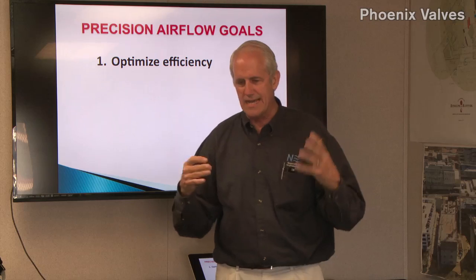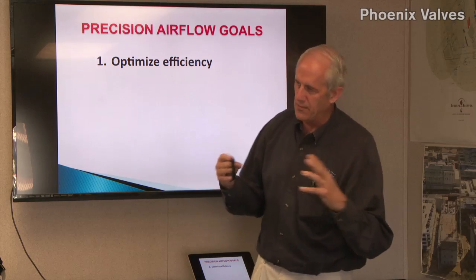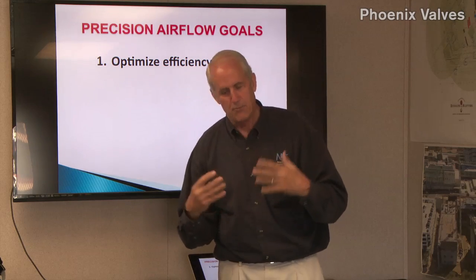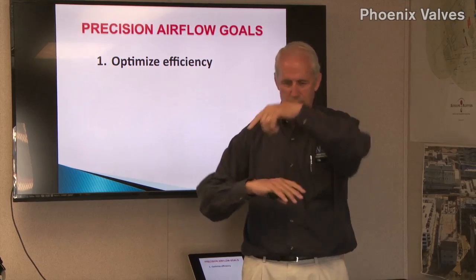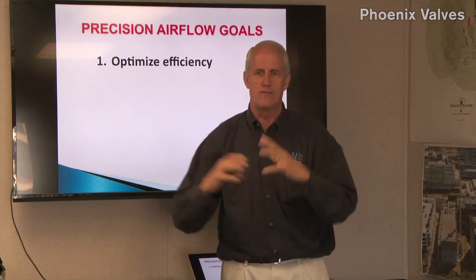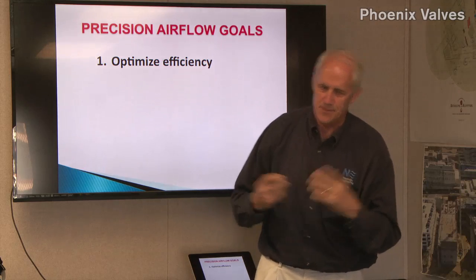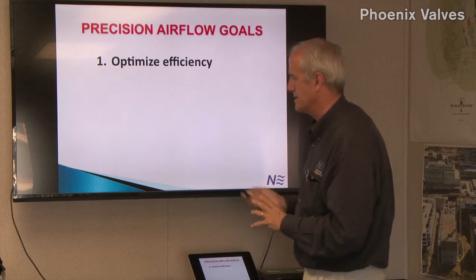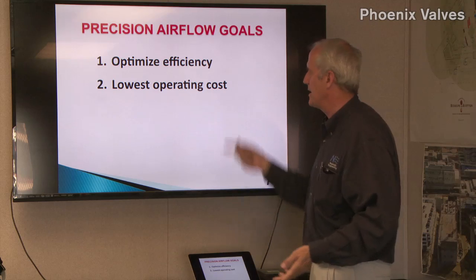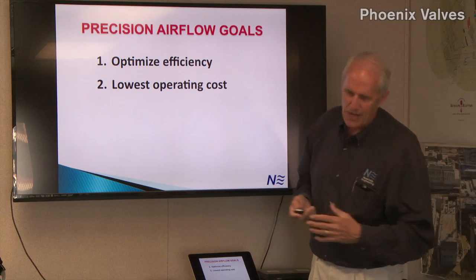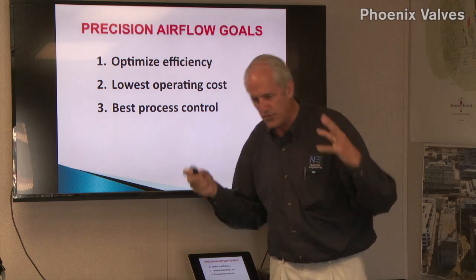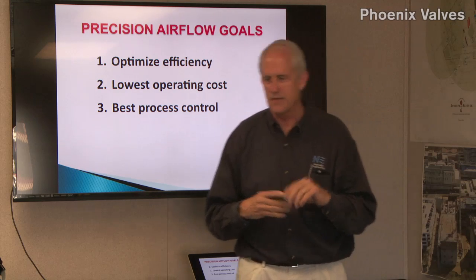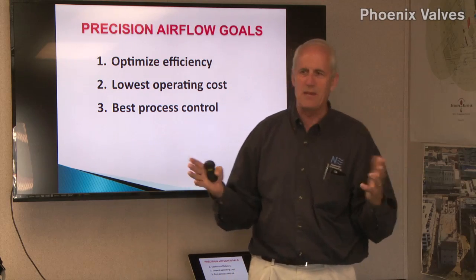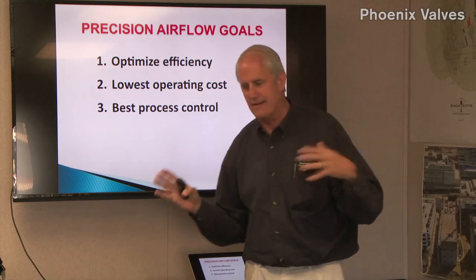So then the question is, how do you respond to it? You do everything you can with your procedures. But when there is an outbreak, you want to make sure that the room gets quarantined, isolated from the rest of the vivarium so it doesn't spread. So that's basically what's going on with the Phoenix valves in this. Anyway, the purpose of the system in general: operate efficiently, reduce operating costs as much as possible, give you the best process control. These animals, vivarium, you just can't be down. Downtime isn't allowed. They need their air all the time.